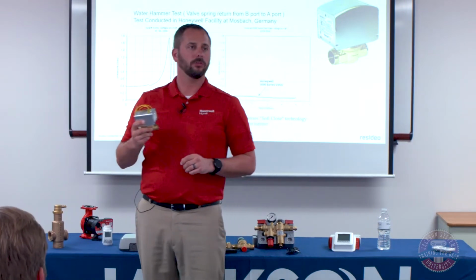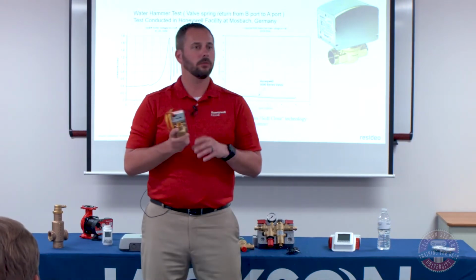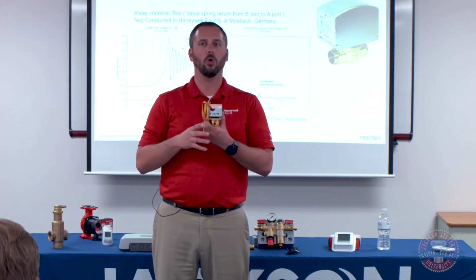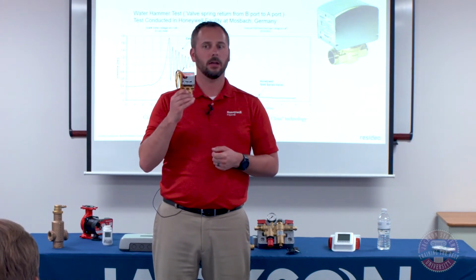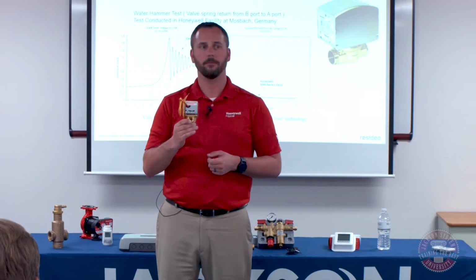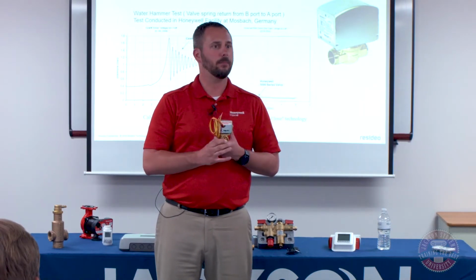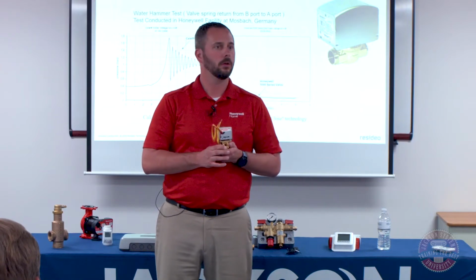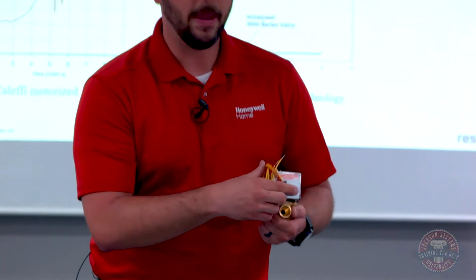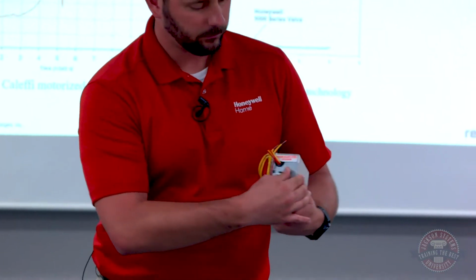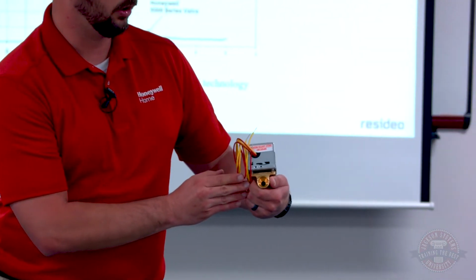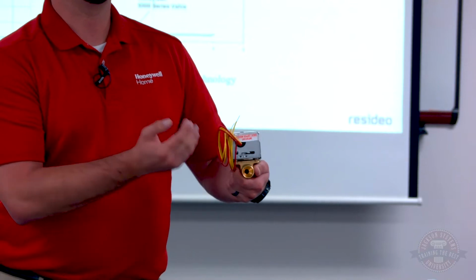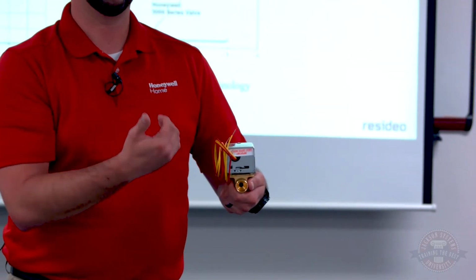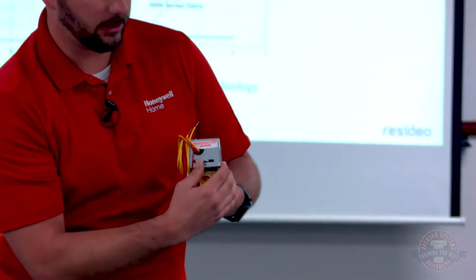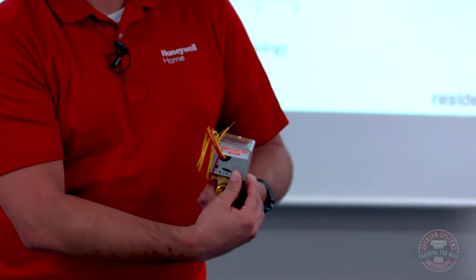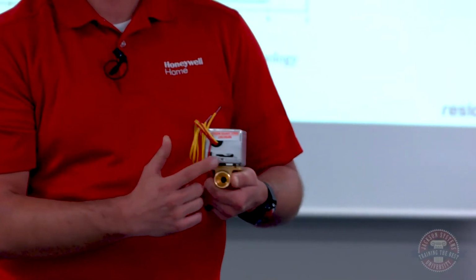Now, one thing I will say, our zone valves, both series, are engineered to only operate when physically and securely attached together. We get calls every now and then from people who say that our zone valve heads are stripped out. We have a manual opener on all of our zone valves, and I'll show you how it works. You'll see it slowly close here. These are normally closed valves, so you've got a spring that always keeps it in the closed position. You can manually open it by just pulling it and pushing it to the side. It actually has a catch, so I can leave it open.